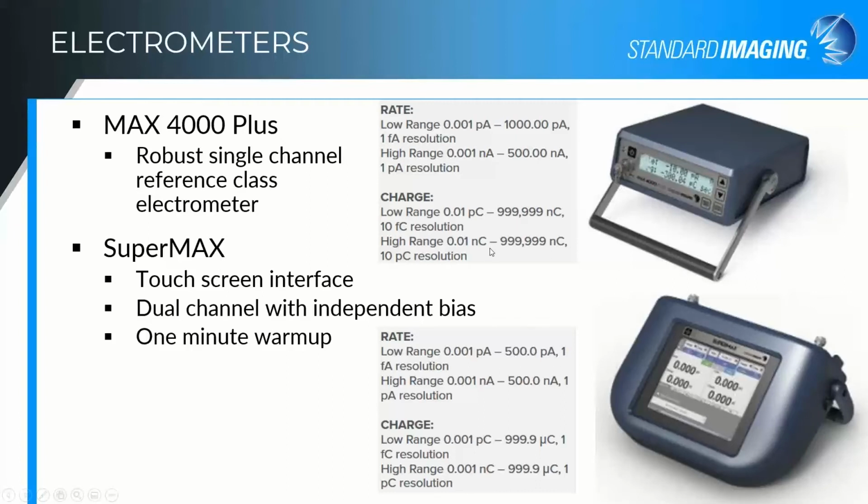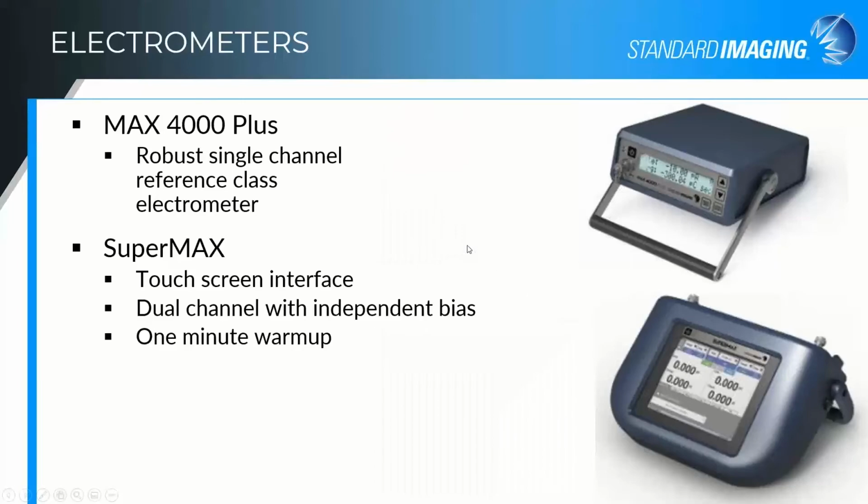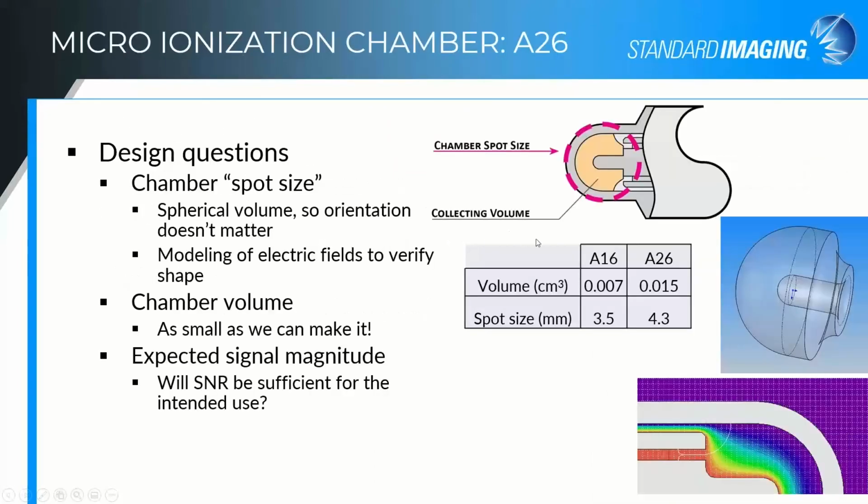There's a question about the smallest field size for the small ion chamber. That really depends on the correction factors that you're using. So just because you can put a field around an ion chamber that fits this field there, doesn't mean that you'll get an accurate measurement. You really do need to correct for that lack of lateral scatter.